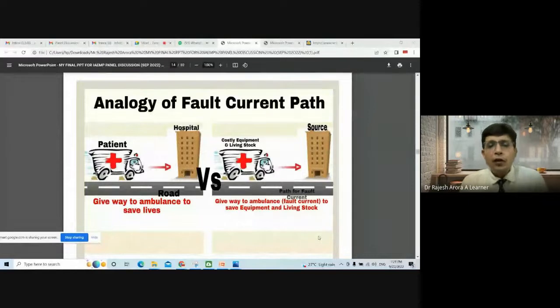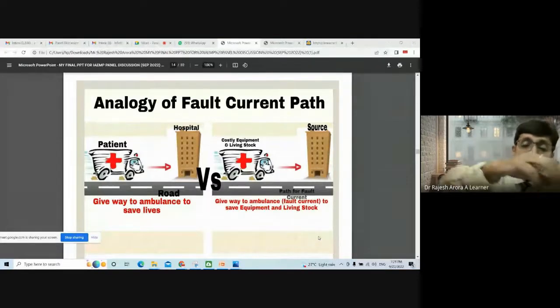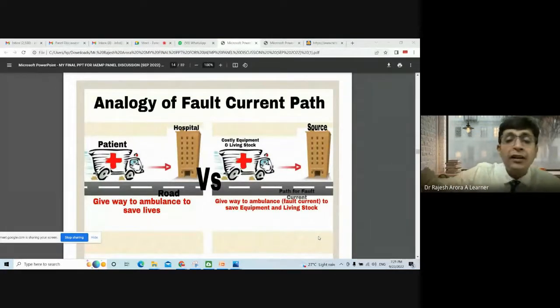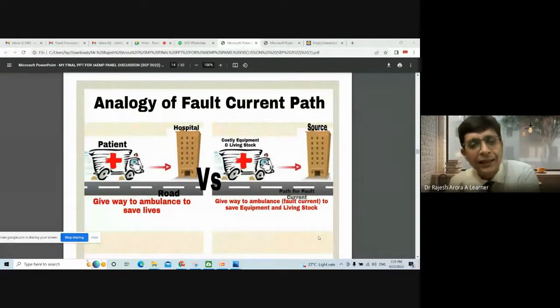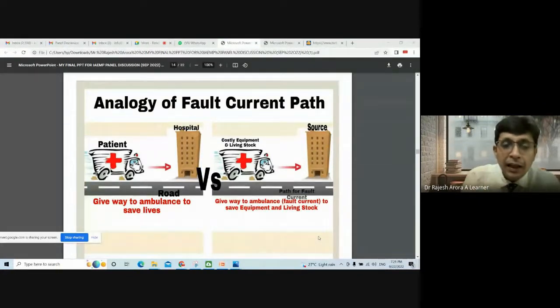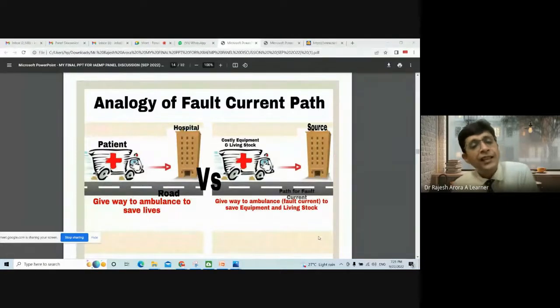This is an analogy of the fault current path. Whenever a short circuit or some fault happens in the system of a residential building, the current has to go back to the source. And the source in the case of a residential building is your main panel. Every short circuit current will have to go back to the panel. When it is going back to the panel, it will definitely flow through the overcurrent protective device. That is your MCB, and that will protect against short circuit.